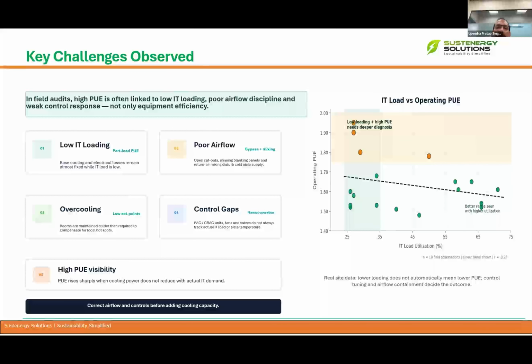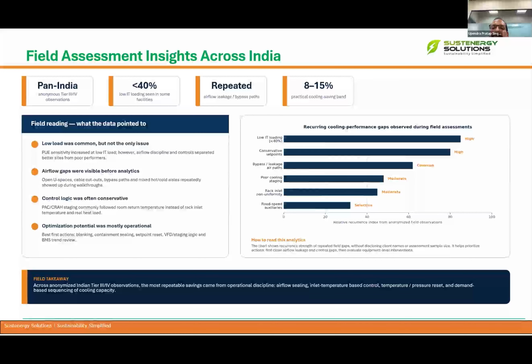Based on the many assessments we did in the various data centers in India, here is the summary we have prepared of what the actual outcome was. It was observed that low load was common, but it was not the only issue. PUE sensitivity increased at low load, but airflow discipline and controls separated better sites from poor performers. That was one of the observations.